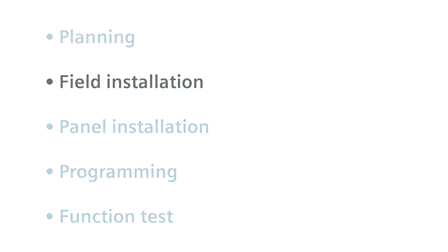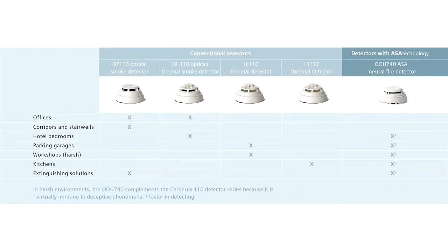Let's start with a short overview about our Cerberus 110 detector series and the field installation. Cerberus 110 is a conventional detector series using the famous algorithm technology from Siemens. By reducing interference from deceptive phenomena like cigarette smoke or exhaust fumes, they provide fast and reliable detection. As a result, the detectors ensure fast response to a wide variety of fire types, especially open and smoldering fires. Let's have a look at the available portfolio.